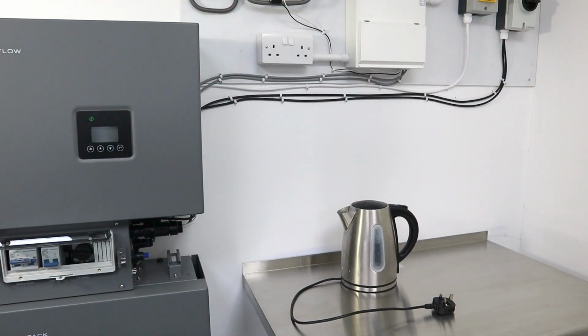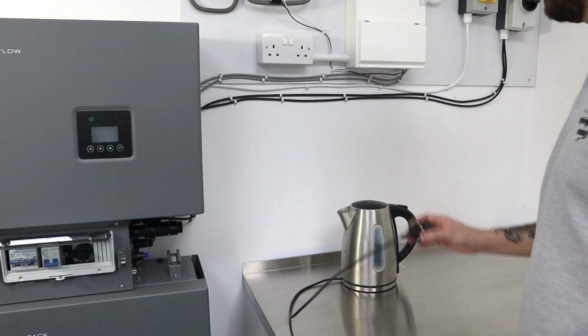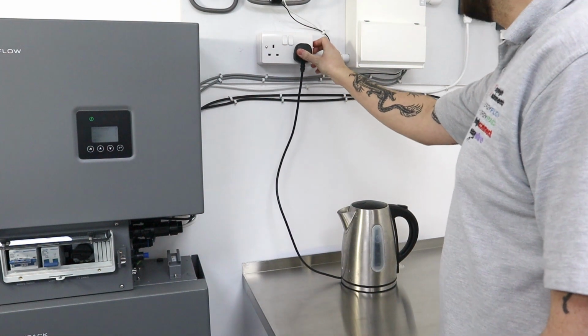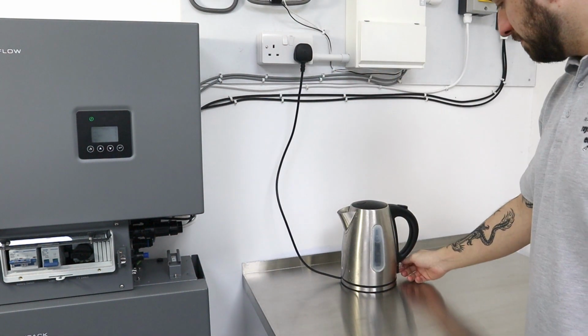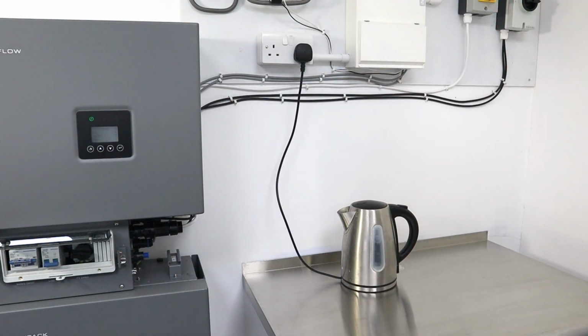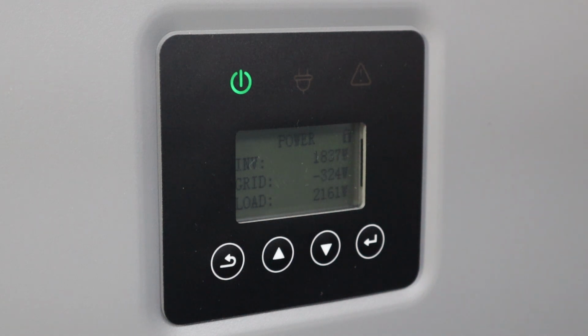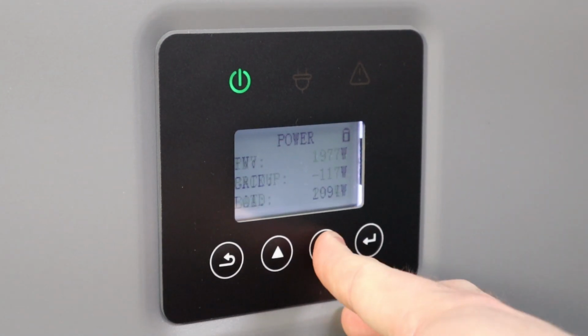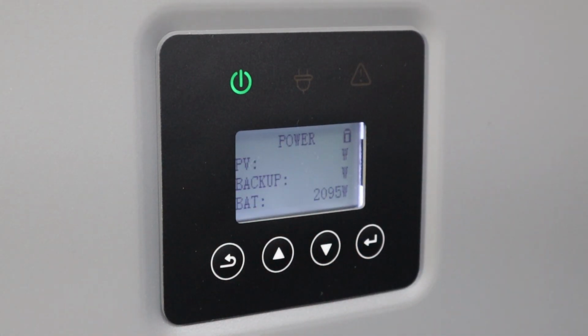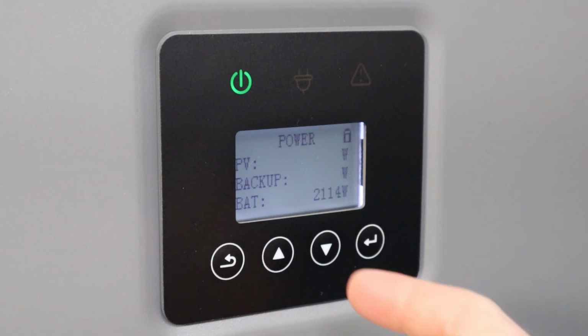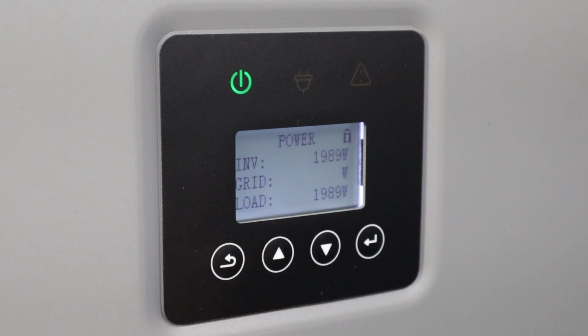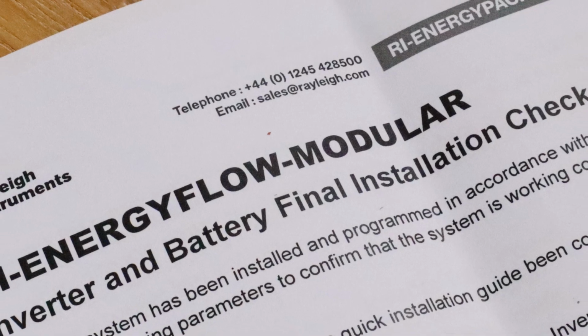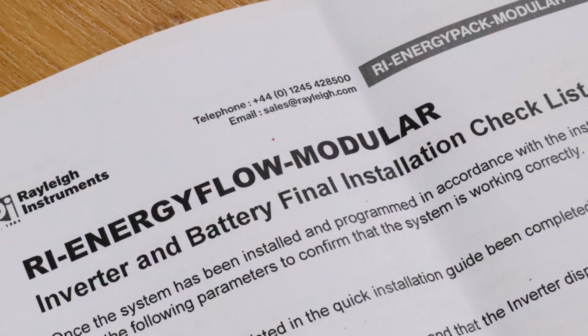The working of the inverter and battery can be tested by putting a load on the system. On the inverter screen, you will see the inverter take over the load from the grid. Press the Page Down button to illuminate the screen and again to see the battery load. Paging up again, you will see that the inverter has fully taken over the supply from the grid. For a full list of checks to carry out, please read the inverter and battery final installation checklist.